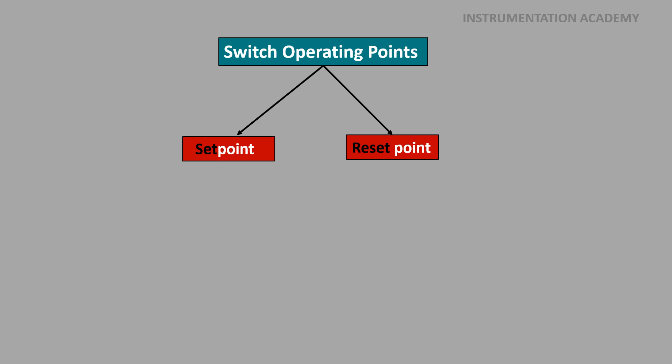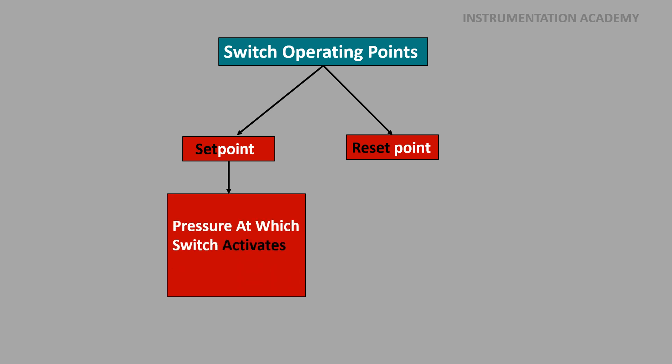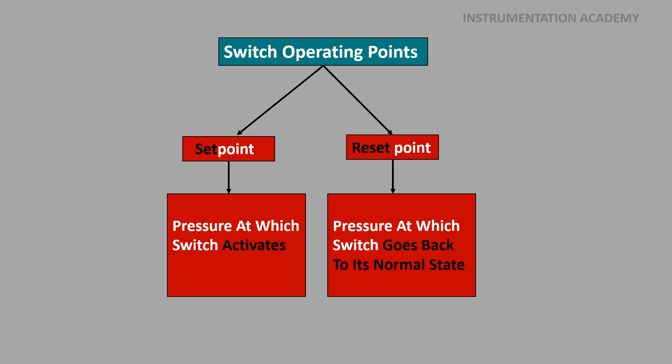All pressure switches have two operating points known as set point and reset point. Set point is the pressure at which the switch activates, and the reset point is the pressure at which the switch goes back to its normal position.